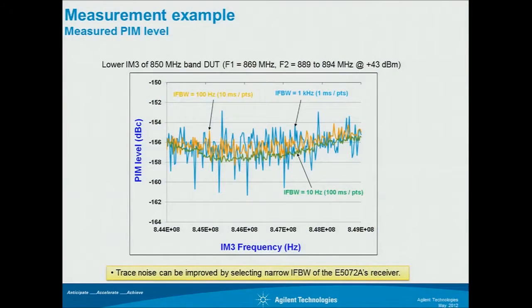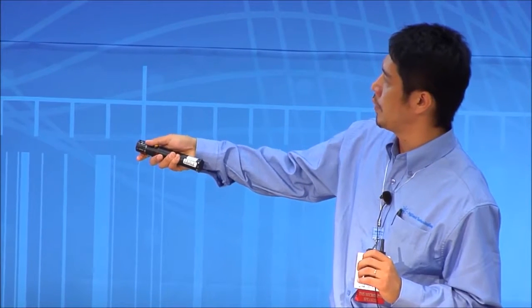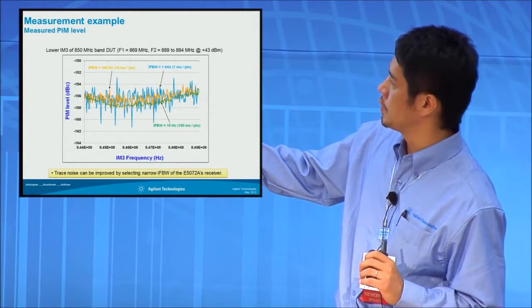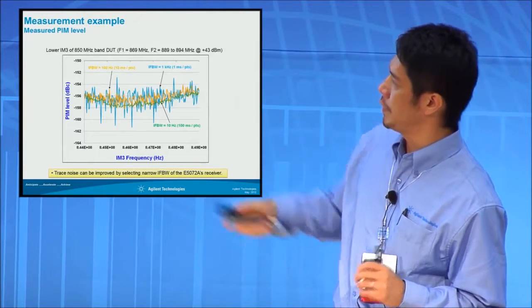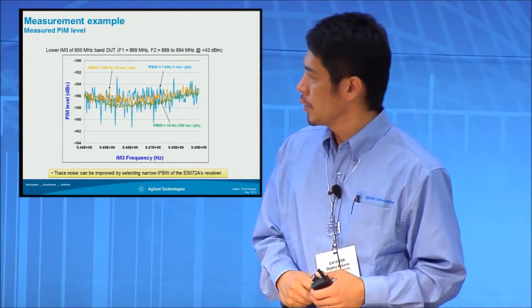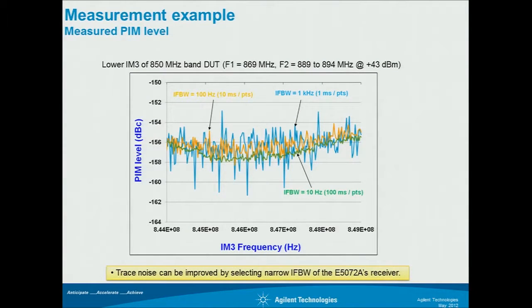This is a comparison of measurement speed and noise level. The green line represents the cleanest, lowest noise level result, with an IF bandwidth of 10 Hz and a measurement speed of 100 ms per point. If you change the IF bandwidth, you can achieve faster measurements, but the noise level will be higher. For example, the orange line has a higher noise level but a faster measurement speed of 10 ms per point. So if you are measuring a PIM level around 155 dBc, a 100 Hz measurement setting would be good enough.